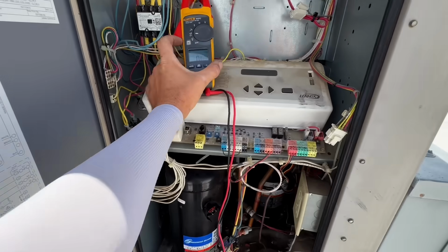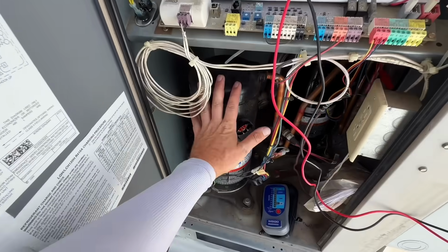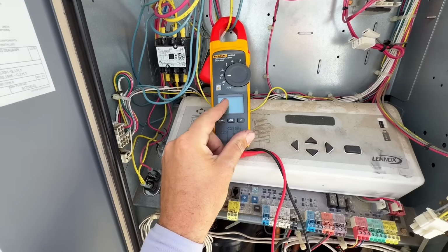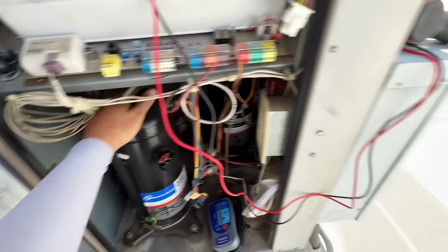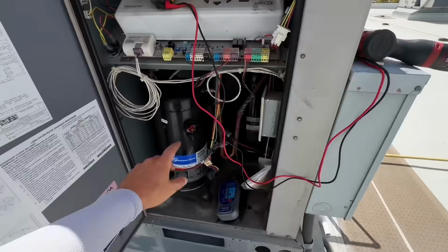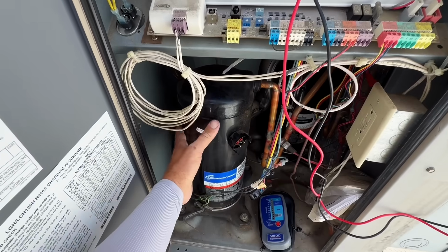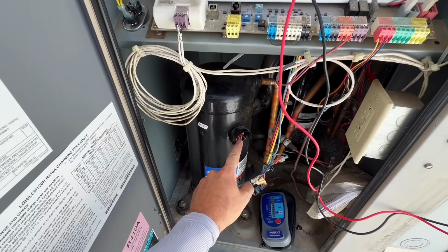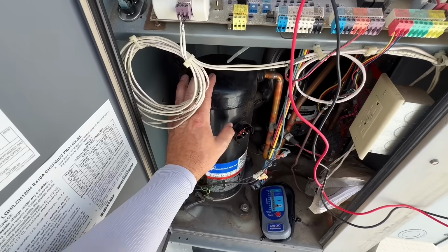electricity, but that's why it's important to do the steps. You go deeper, you use your instruments. One thing, before you condemn a compressor that is reading OL, make sure that the compressor is not hot. And if it's hot, use some water like we have over there. Cool down the compressor, because sometimes when they overheat and they lock out on thermal overload, it will read OL on your windings. So you don't want to misdiagnose a compressor just because it's hot and overheated.